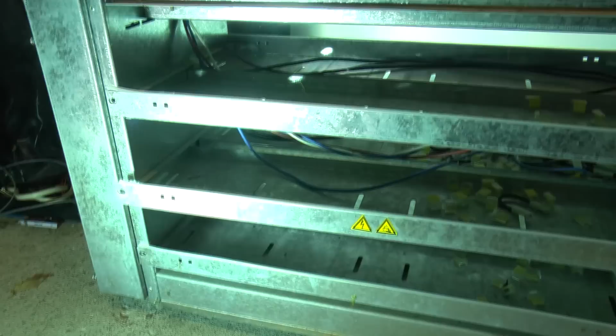And at the bottom we've got 3 battery trays, and in fact if you look through there's another 3. We've got 6 battery trays. The reason it's not got any batteries in it now is that it uses 46 batteries. In fact, it came to me with 46 batteries in it, which were all old and knackered. It can be configured for between 30 and 50 batteries in series as one big long center tapped string. Now the batteries I've been using to test the other UPSs were 12 years old. They didn't have a lot of grunt in them. You can see as soon as I got them to do very much at all, they just packed in.